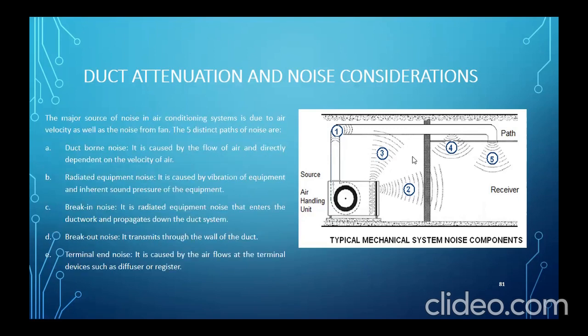So, the major source of the noise in air conditioning is due to the air velocity as well as the noise from the fan. Sa fan is yung vibration. Ito naman sa ducting is velocity. The 5 distinct paths of noise are: A, ductborne noise, yung 1. It is caused by the flow of air and directly dependent on the velocity of air. B, radiated equipment noise. It is caused by the vibration of the equipment and inherent sound pressure of the equipment. C, break-in noise. It is a radiated equipment noise that enters the ductwork and propagates down the system. D, breakout noise. It transmits to the walls of the duct. E, terminal noise, terminal end noise. It is caused by the airflows at the terminal devices such as diffuser or register.